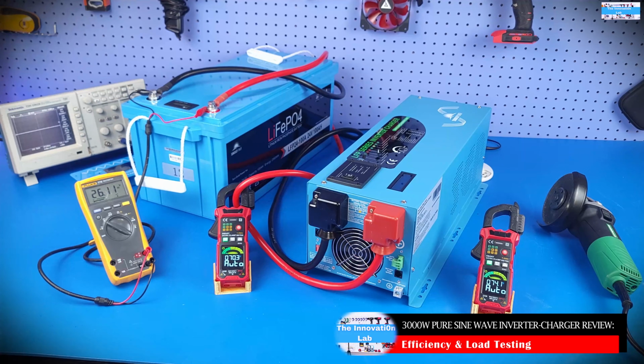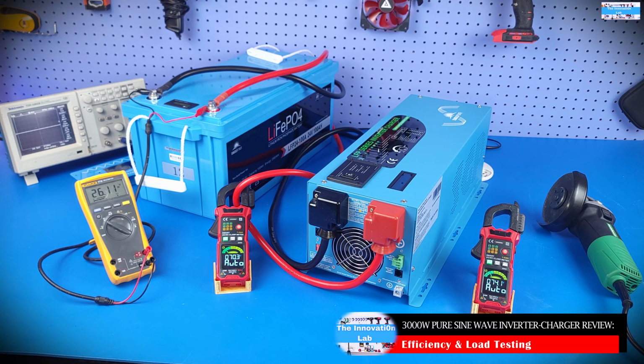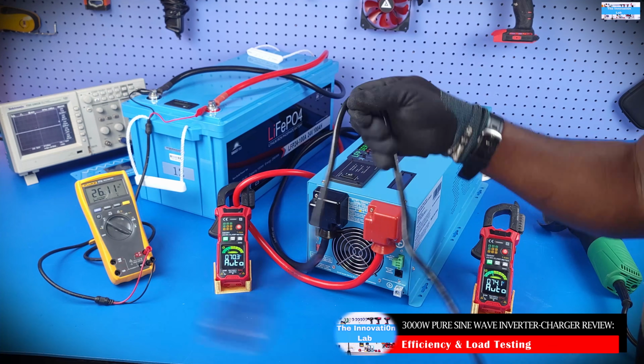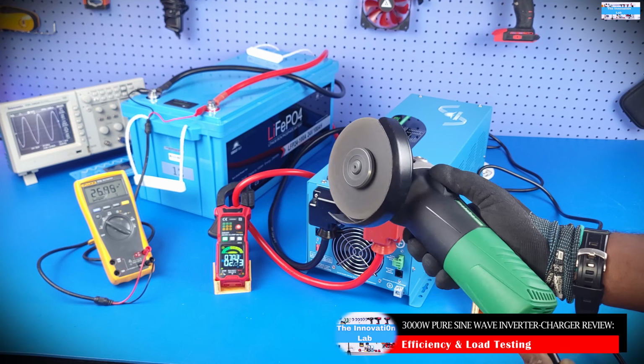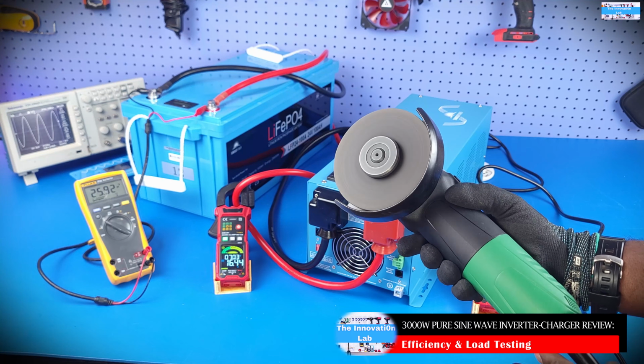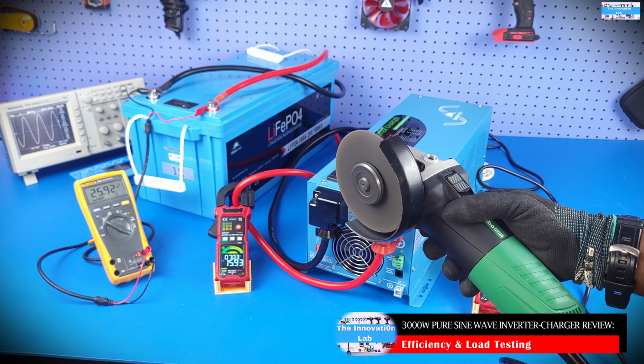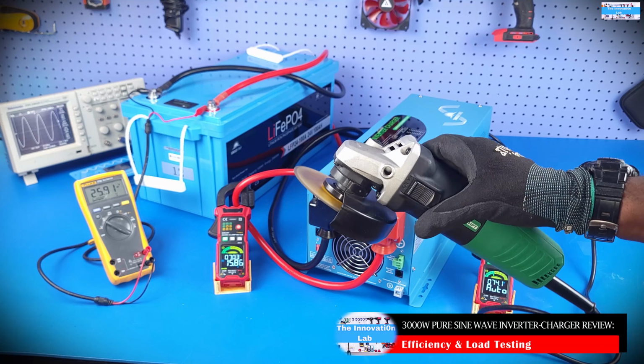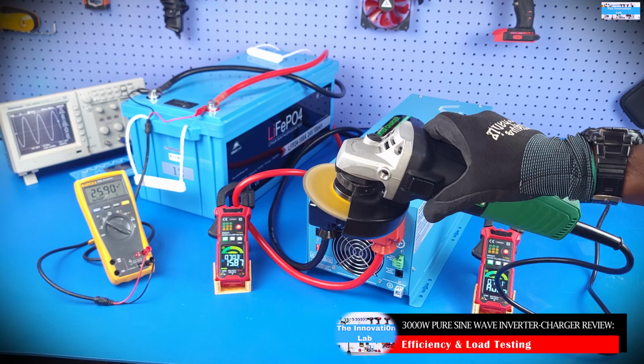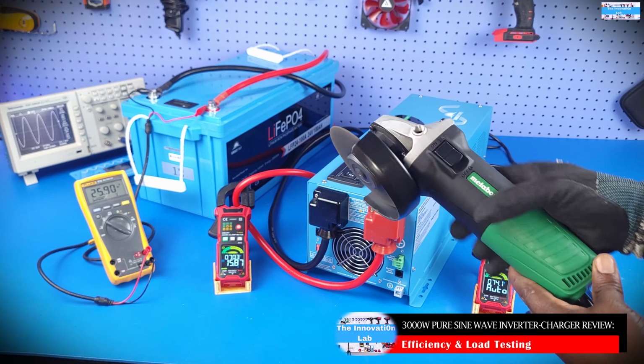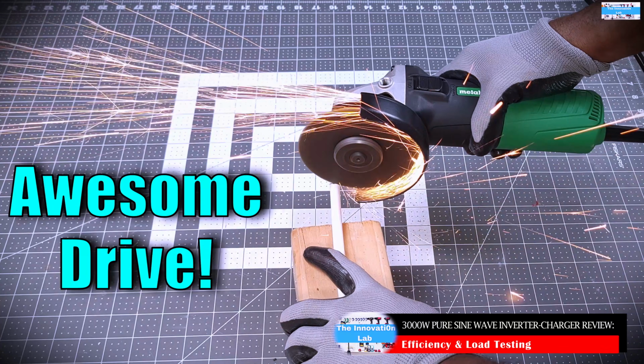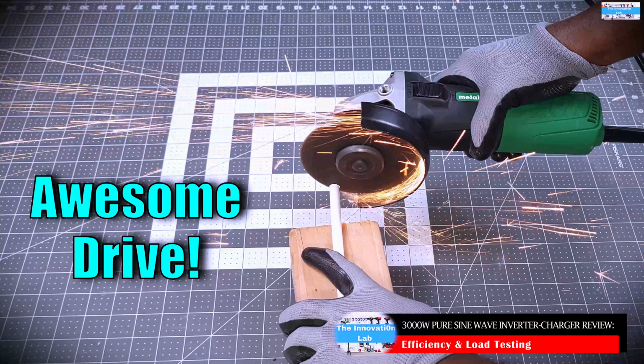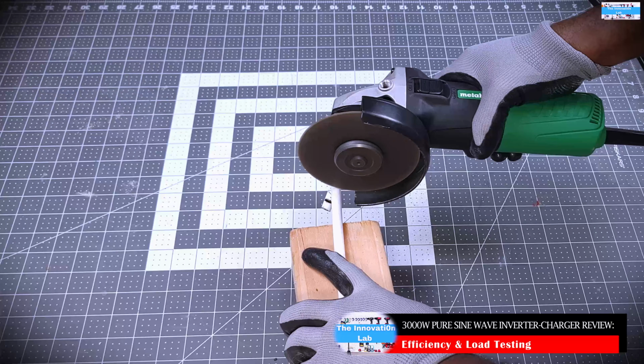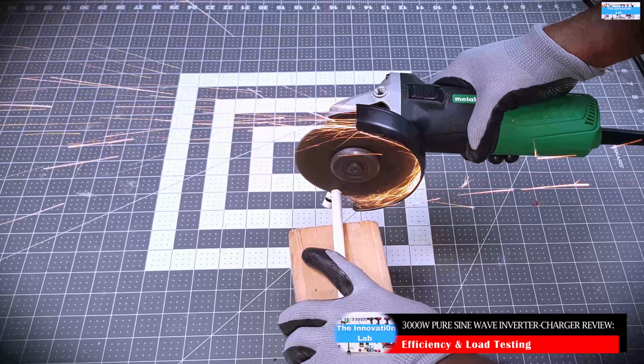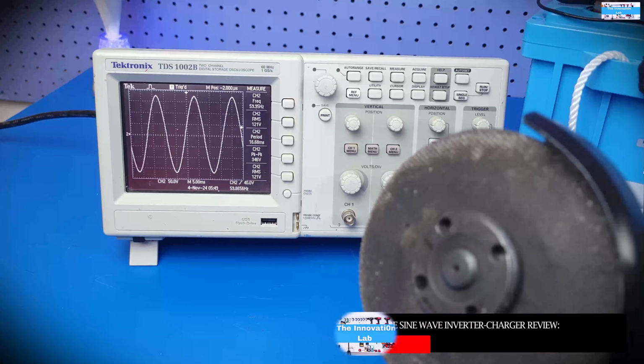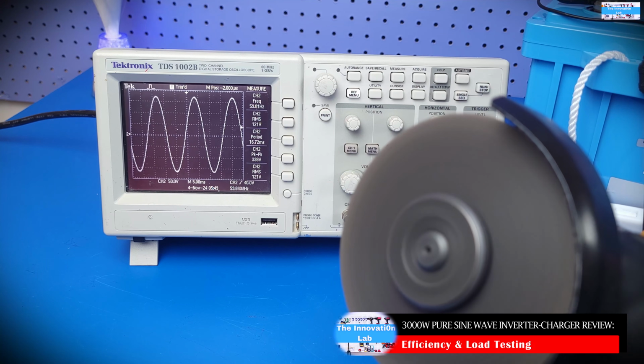For the second test load, I wanted to see how this power inverter would respond to an inductive load, so we used it to drive our electric grinder. There's a little bit of harmonic distortion when the grinder starts up, but after that it was smooth sailing, no issues, no distortion on the sine waves. Even when we applied load on the grinder by using it to do some cutting, the waveform stayed the same with no distortion. I only saw distortion when the grinder kicks in, and after that no issues at all.